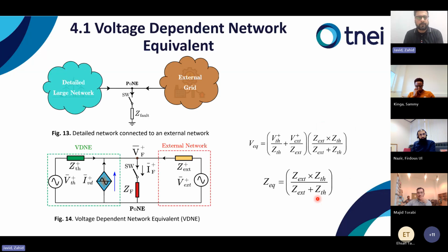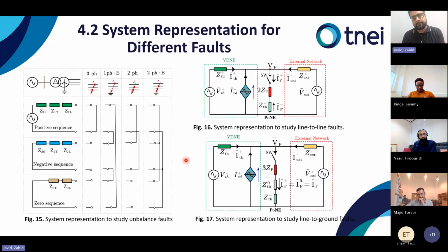For example, consider an external grid on the right side, and a detailed large network on the left side, and there is a point of network equivalent where both systems are connected. The external grid is made of conventional sources, so we can just represent it with a voltage source behind impedance. But on the left hand side, we have some IBR units that have a nonlinear response, so we cannot model them as a voltage source behind impedance. So we model them as a voltage dependent current source, where the current actually depends upon the voltage at this point, and this voltage varies when the fault impedance varies. This is the network equivalent we use. This is for positive sequence, and for other faults we can have different representations.